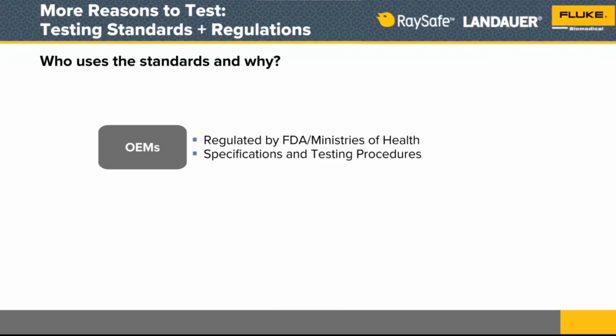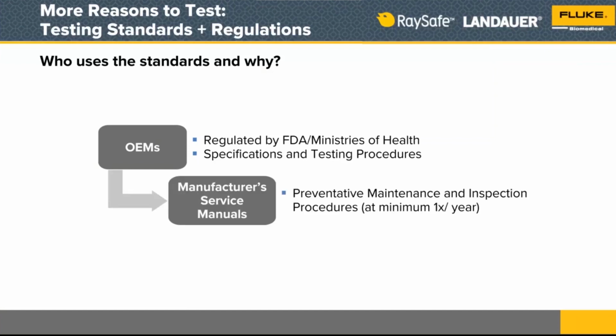So this standard is designed for me to be able to collect information about the design and the functionality of my infant incubator. And it goes along with clinical studies that are done as proof statements there as well. So design validation is what it's intended to be focused about. Well, then those manufacturers take the design validation tests and they use them in identifying the brand and model specific test procedure that you will find in the service manual for that particular infant incubator make and model.